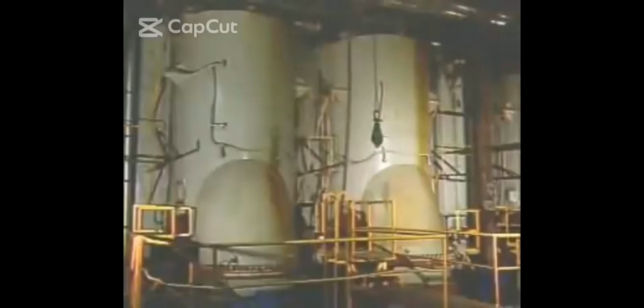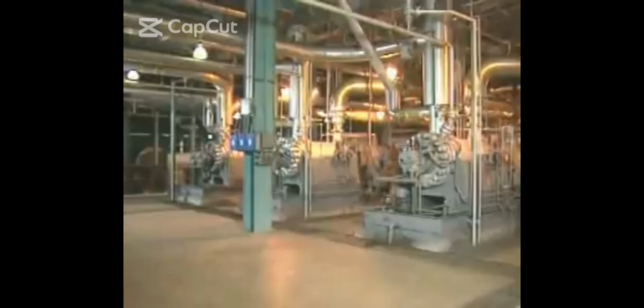The rest of the steam is exhausted from the turbine to a main condenser. Condensate from the main condenser goes through the condensate system and becomes feed water that returns to the boiler through the feed water system. In this way, the condensate and feed water system work together to supply water at the proper rate to support normal boiler operation.